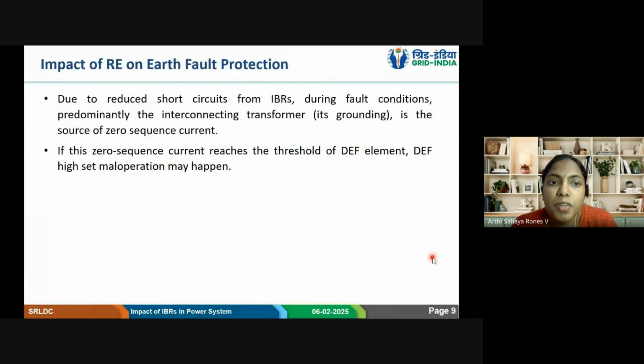First protection issue that I want to highlight today is about the impact of the RE on the earth fault protection. So in transmission system, we have the earth fault protection, mainly to take care of the high resistive faults. Otherwise, the main protection is distance and differential protection. So earth fault protection is to take care of the high resistance fault in the system. So with the IBRs, what happens to this earth fault protection? We are going to discuss now.